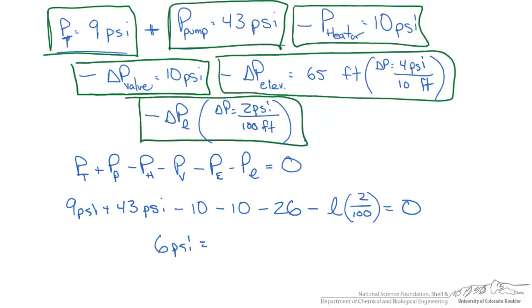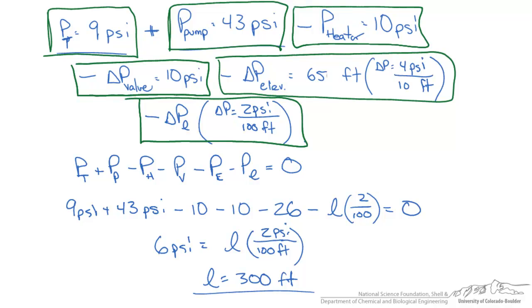We're left with 6 psi equals L times 2 over 100. This means our L is going to be 300 feet. So for this problem, our estimated maximum length of the pipe is 300 feet, given our pump capacity and the losses associated with the components in the system.